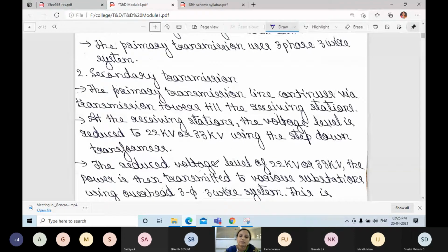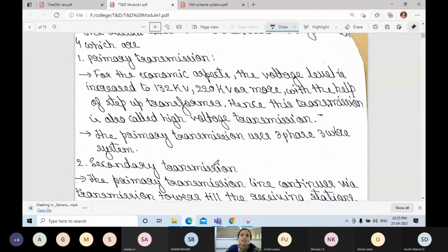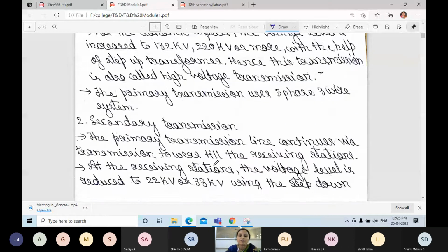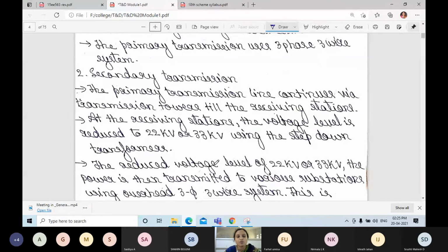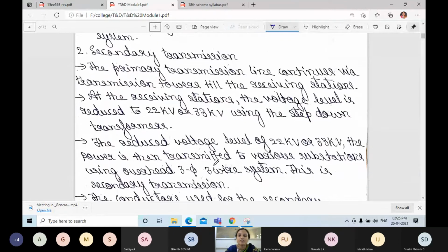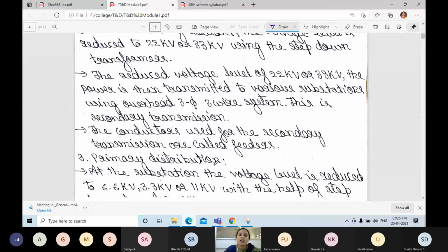Next is secondary transmission. The primary transmission line continues via transmission towers to the receiving stations. At the receiving stations, the voltage level is reduced from 220 kV to 22 kV or 33 kV using a step-down transformer. At the reduced level of 22 or 33 kV, the power is then transmitted to various substations using a three-phase, three-wire system. This is secondary transmission, and the conductors used for it are called feeders.